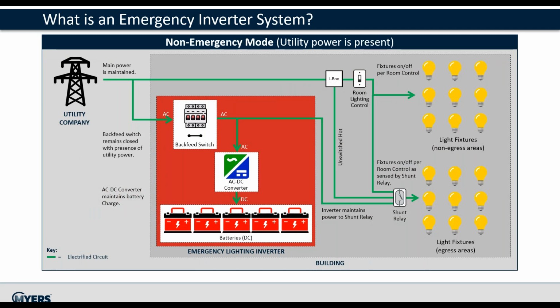The next couple of slides will illustrate the wiring and operation of a fast transfer inverter system from the utility source through to the load. During normal operation, the backfeed switch is closed, allowing power to feed directly to the load, as well as the AC to DC converter, which is keeping the batteries float charged. The non-egress areas have standard wiring and operate as a normal lighting circuit.